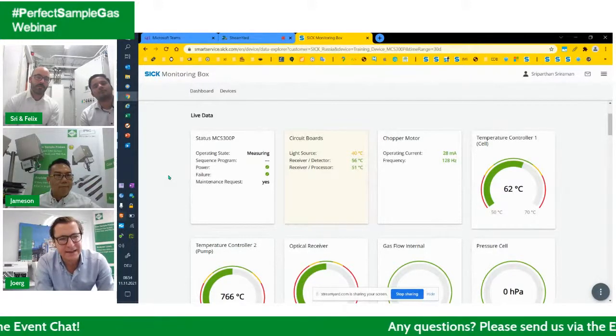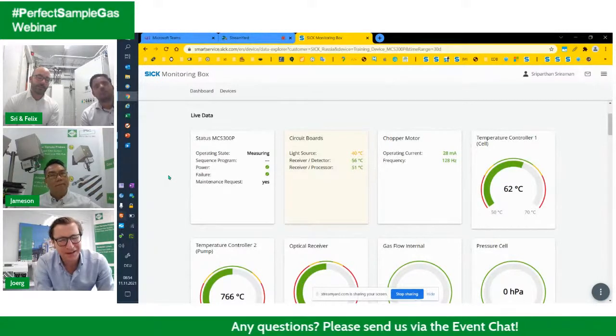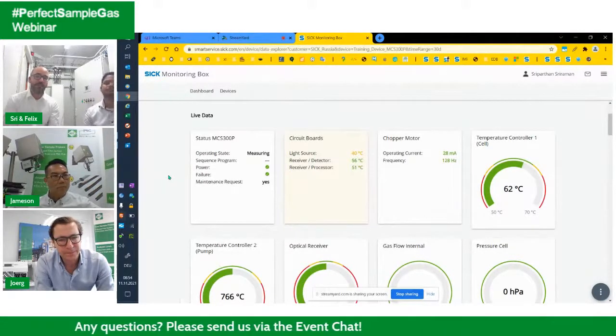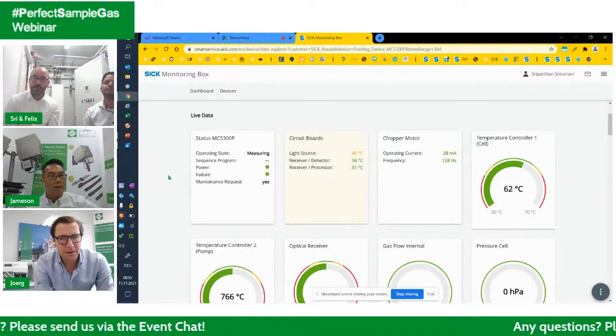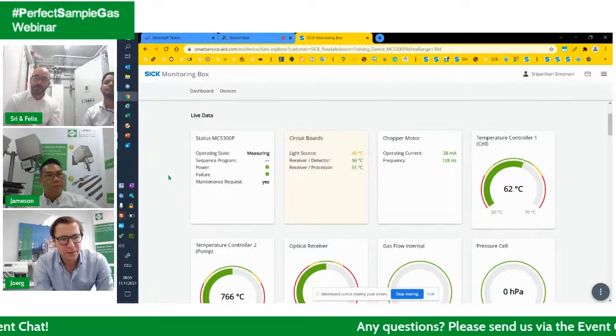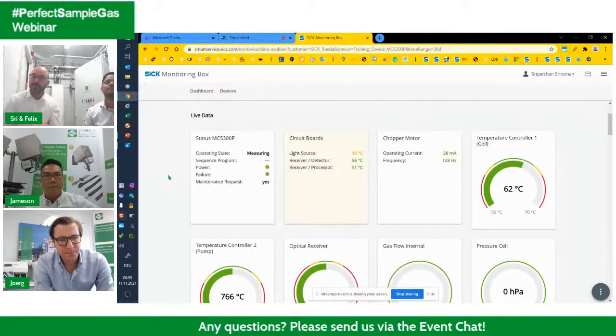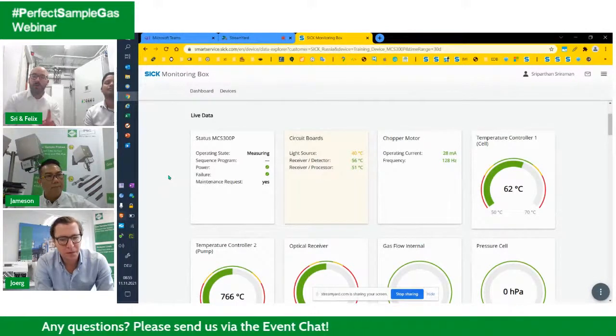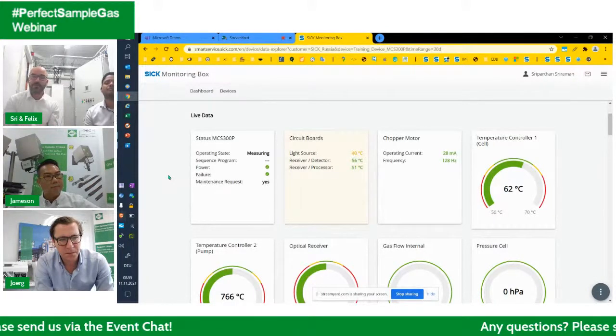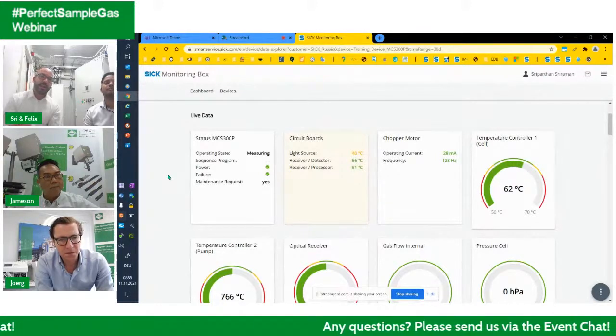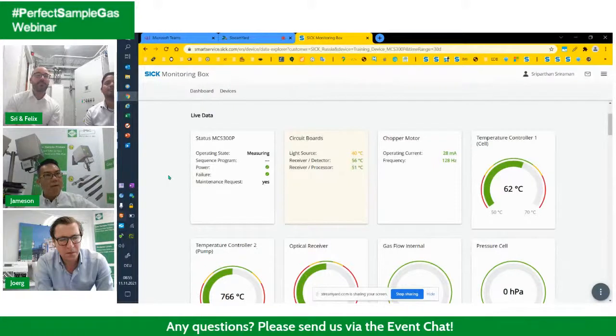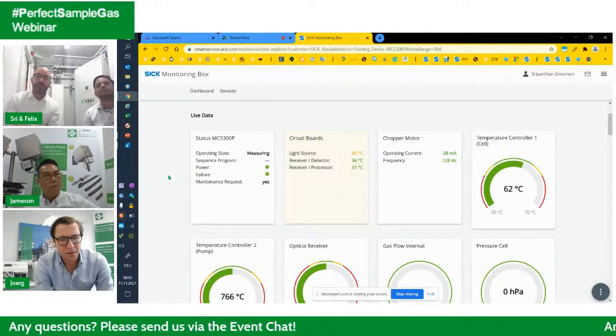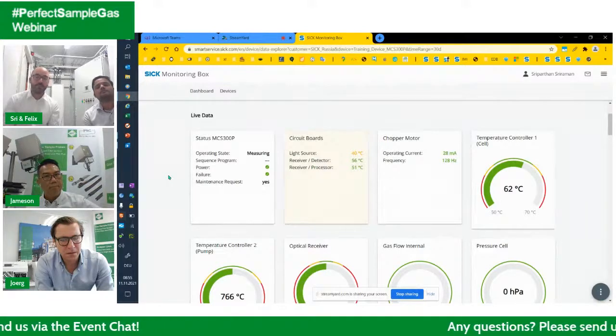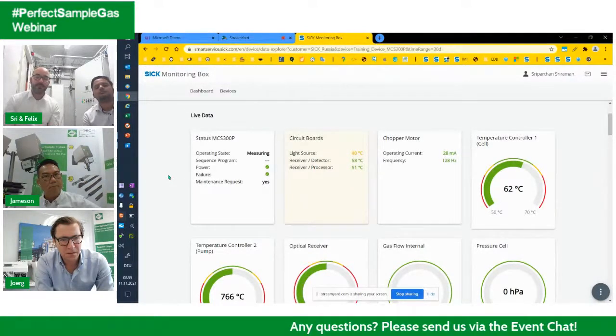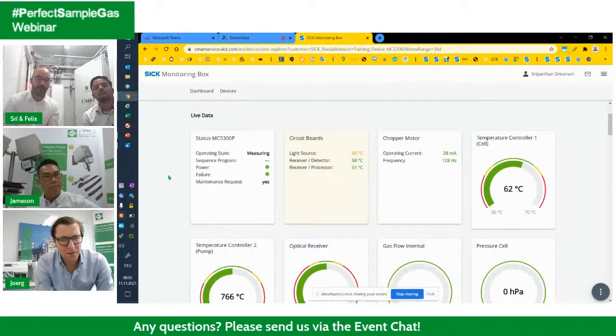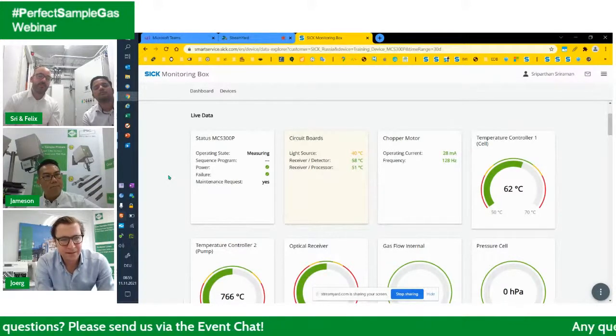So you call this the vital data of the system. Exactly. We distinguish between the measurement data—these are the usual values like gas concentrations, which are needed in order to put a report together—but there is also what we call the vital sensor data. Those are the temperatures, flow, amperage, voltage, power consumption. This is data which has been generated before but was not used in a proper way. Using these new technologies, we are able to connect the different dots to also see dependencies of different measurement values which have not been used up to date, and create an additional benefit for the customer and also for us.